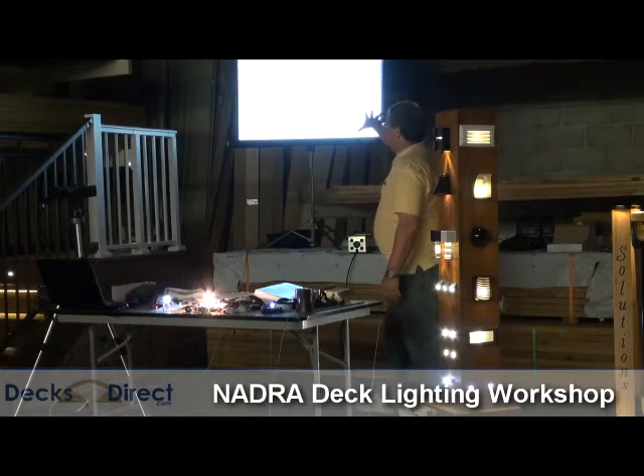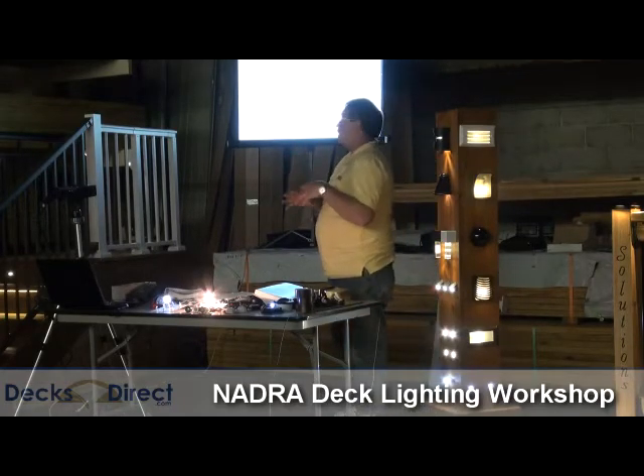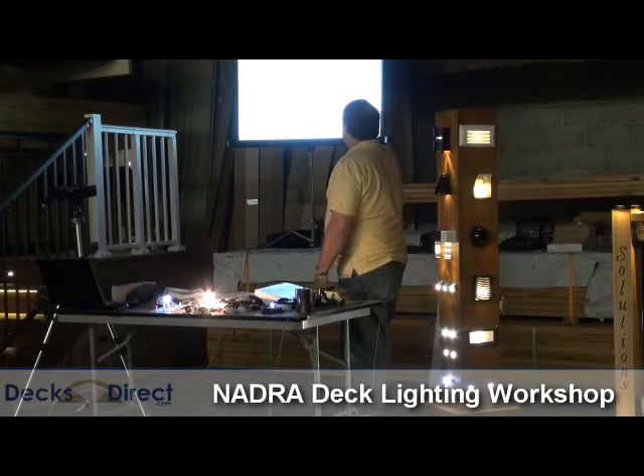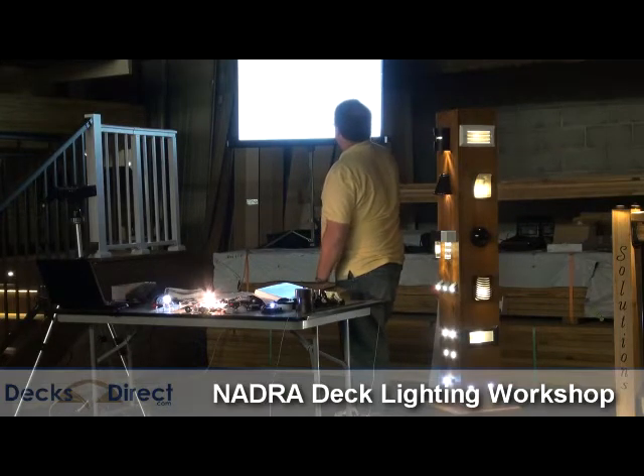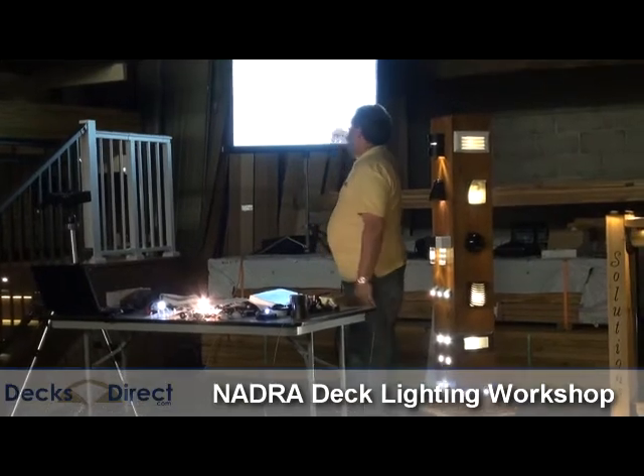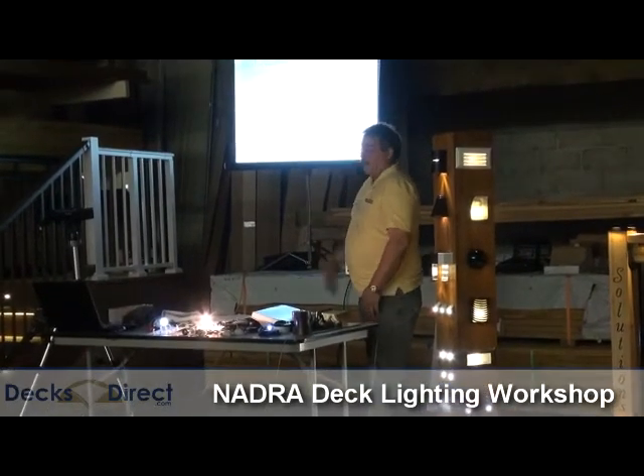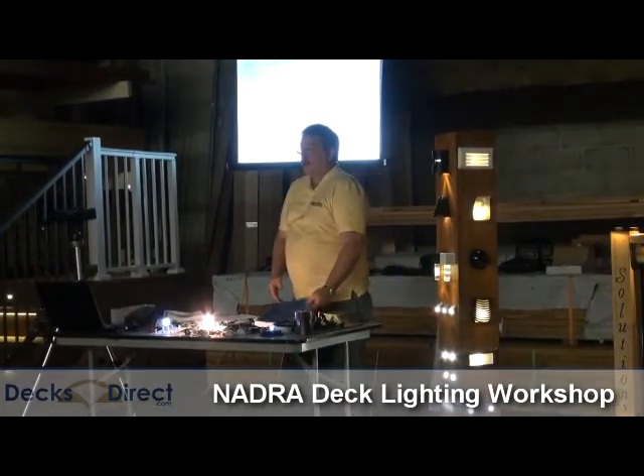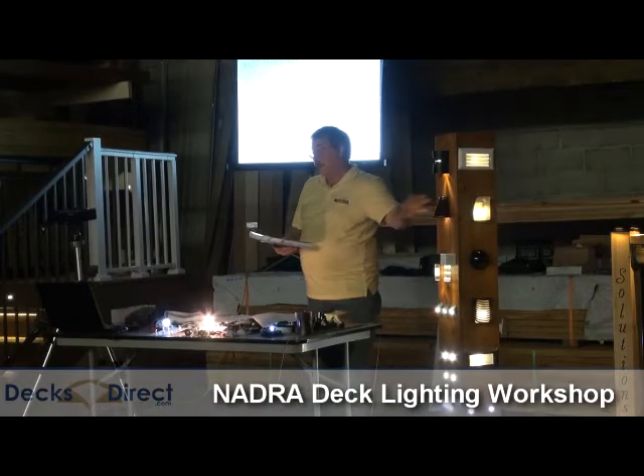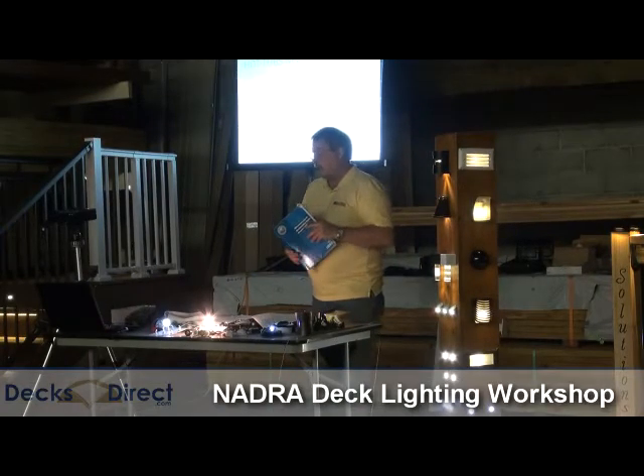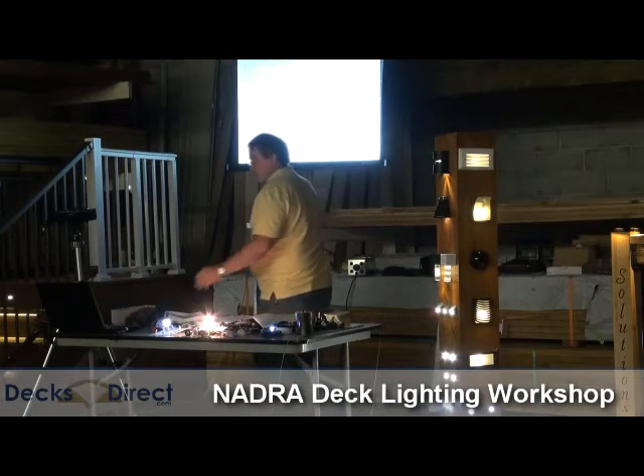Again, the GFI doesn't work. Even though you're plugging your transformers into those GFI outlets, it's not affecting the transformers. It's a separate isolated circuit. Switching devices all have to be 5 feet away. All lighting fixtures and outlets have to be a minimum of 5 feet horizontally and 12 feet above the surface. So keep that low voltage stuff away. You put a light in your deck and somebody gets hurt, they're going to come back to us and ask us to resolve that issue.